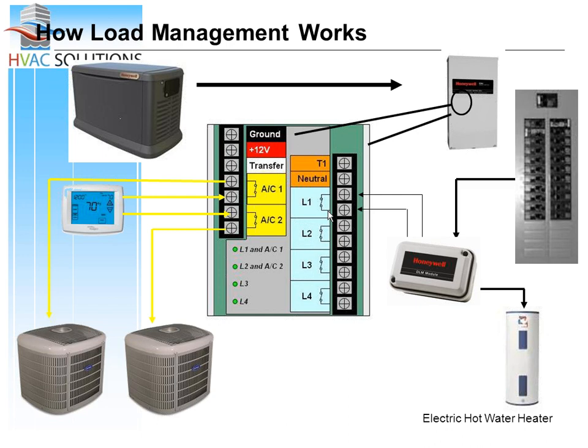The benefit to that is that a lot of codes will allow 24 volt wires to be run in the, I'll say, surrounding areas of that transfer switch. So you're able to do a lot more work without having conduit. So older switch, it's a 110 and you need a DLM module. The new switch, both sides are 24 volt and you still need a contactor, but it's in a kit that also comes with a transformer to allow you to do 24 volt work.